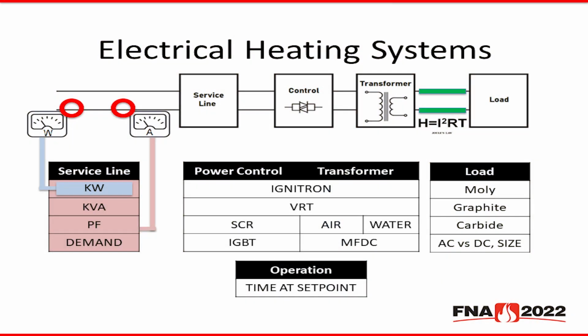The ammeter describes how kVA is a better way to understand power, because kVA is actually what determines the amperage and current going through your system. And this is what you get billed for peak demand charges, as well as circuit breaker sizing in a system. So the first part of a power control system is the power controller.